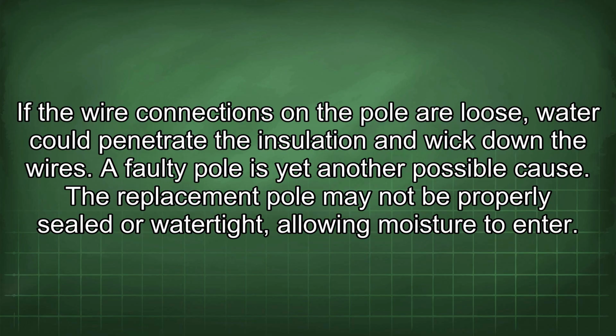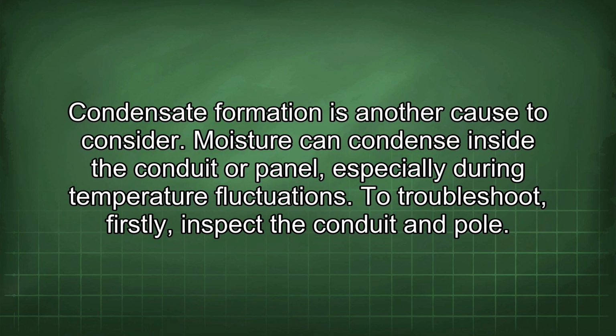A faulty pole is yet another possible cause. The replacement pole may not be properly sealed or watertight, allowing moisture to enter. Condensate formation is another cause to consider. Moisture can condense inside the conduit or panel, especially during temperature fluctuations.